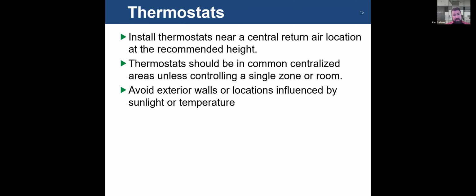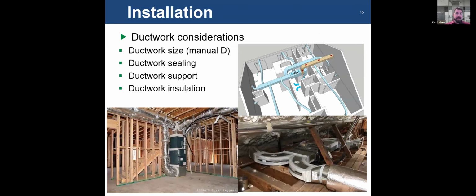Thermostat installations. Install thermostats near central return air locations, pretty common. Make sure they're in common areas. If you put a thermostat in a room and shut the room door, that thermostat's going to be influenced by the air in that room alone and not the rest of the house. Avoid exterior walls or locations influenced by sunlight or temperature. Seems straightforward, but take a look around before you put a thermostat on a wall. Make sure you're not in the hallway at the upper floor with a big window that's going to allow light to shine on it for 3 hours out of the day. Definitely try to avoid the exterior walls. The exterior wall will influence the temperature that thermostat actually sees or senses.